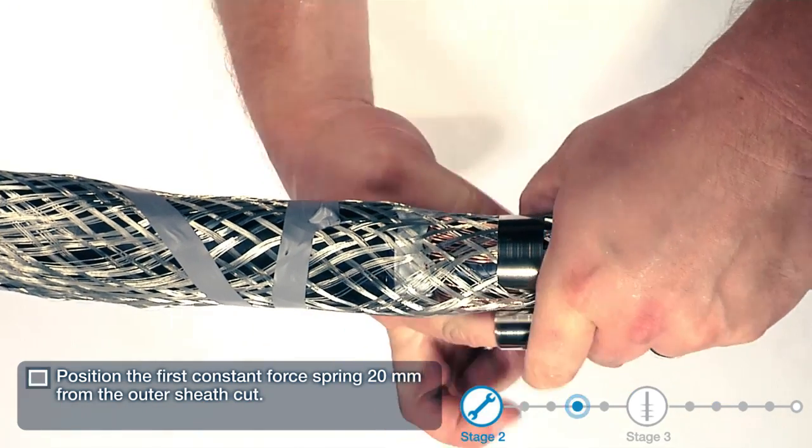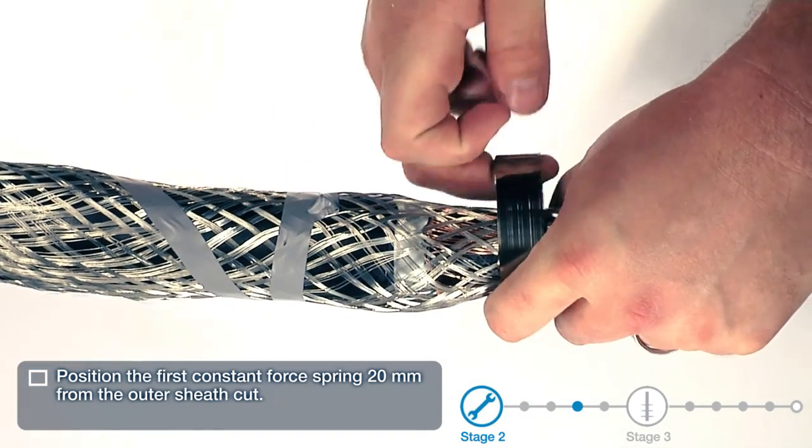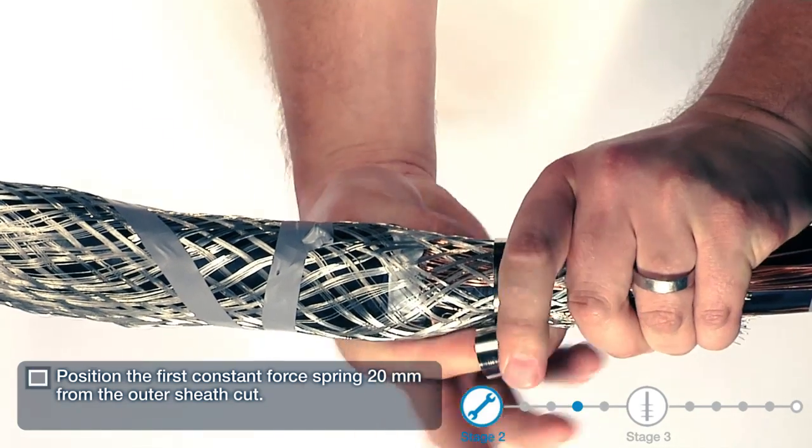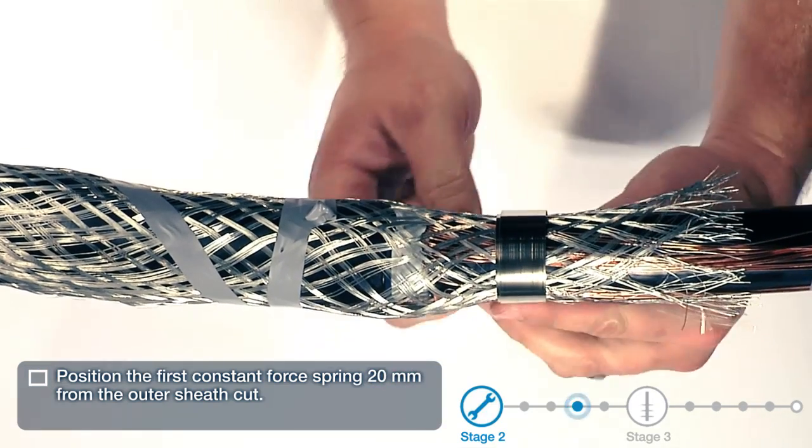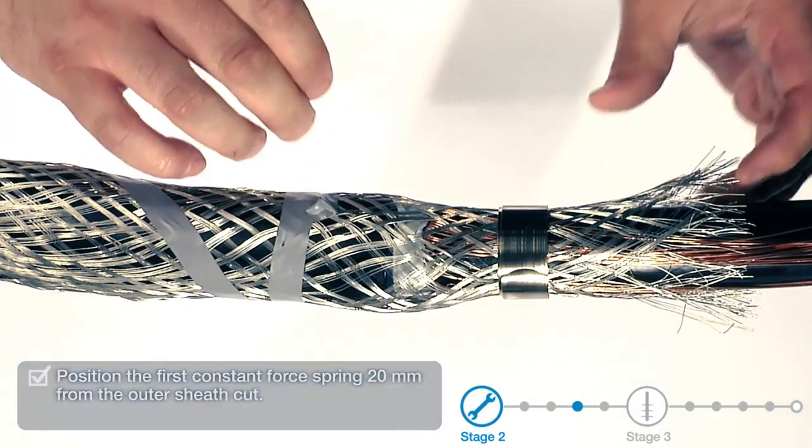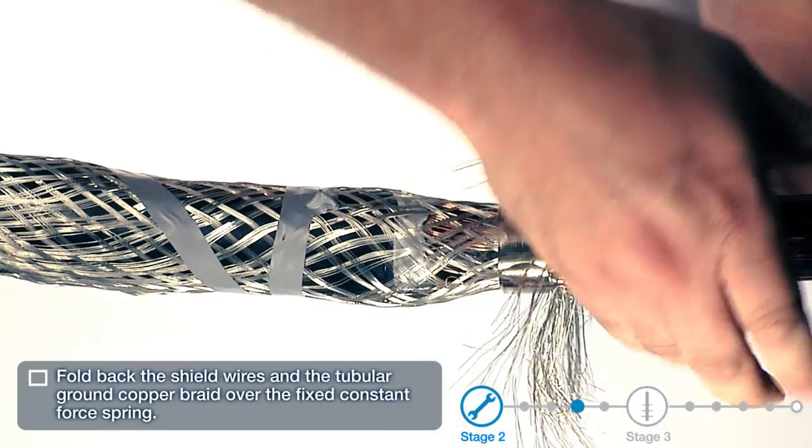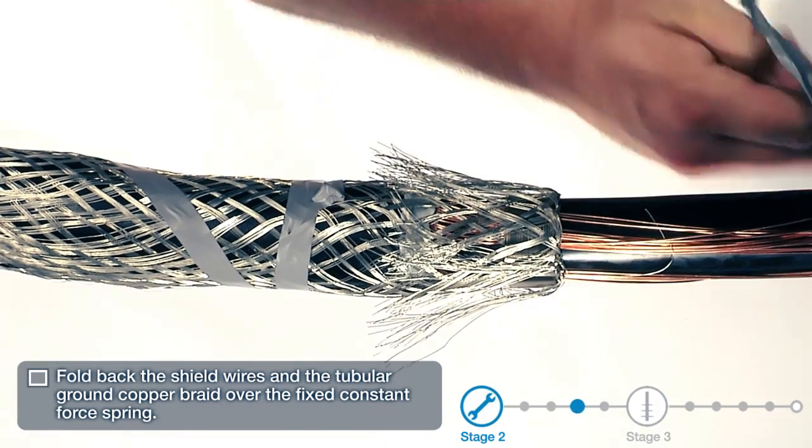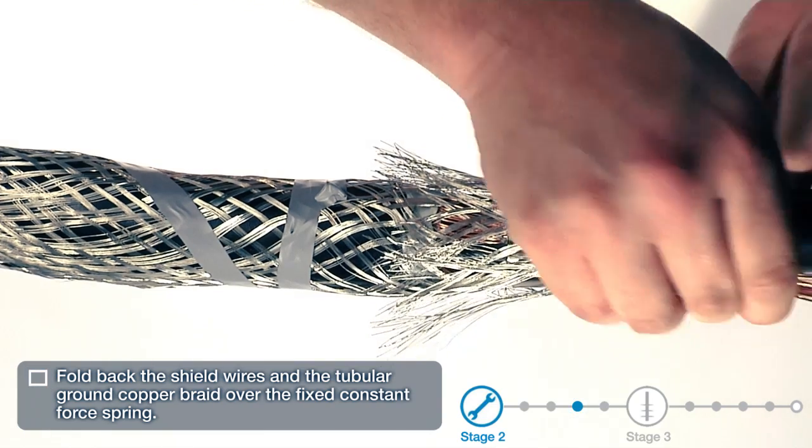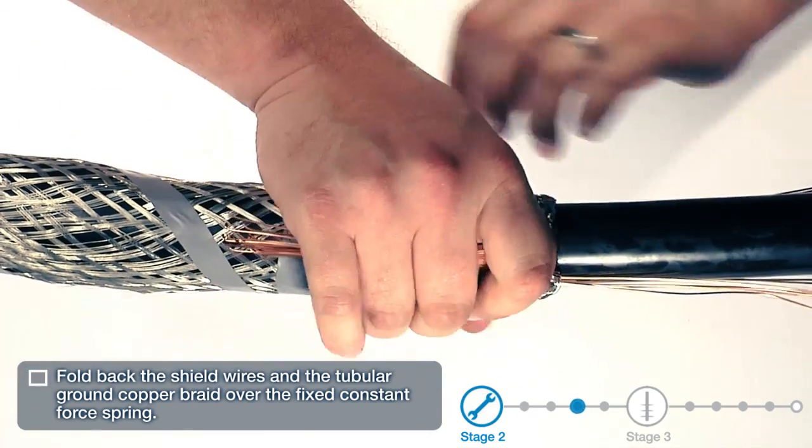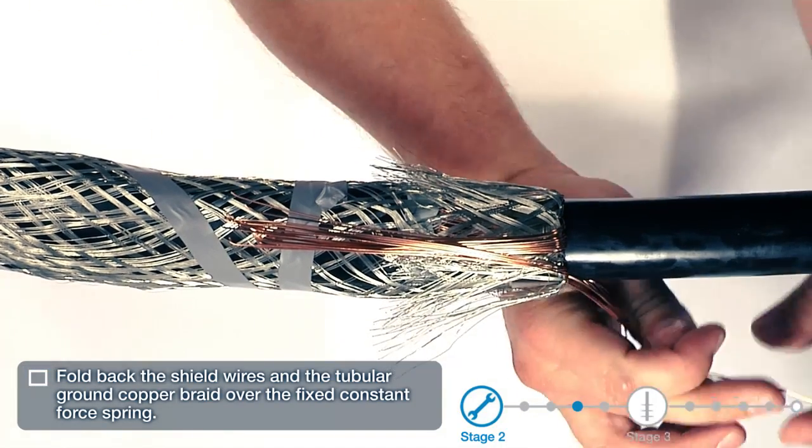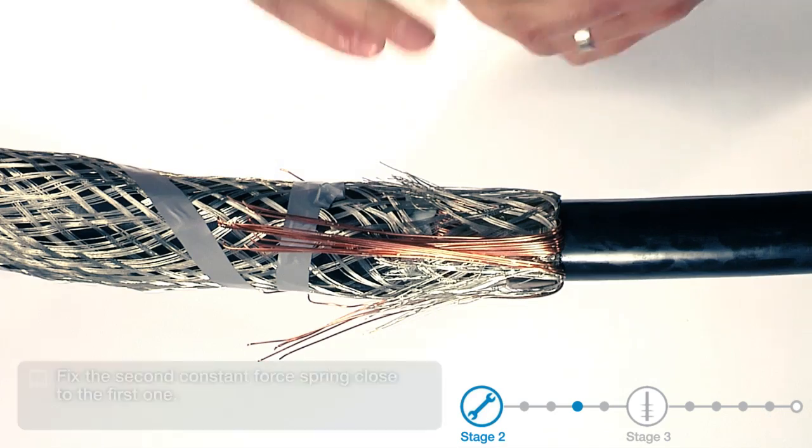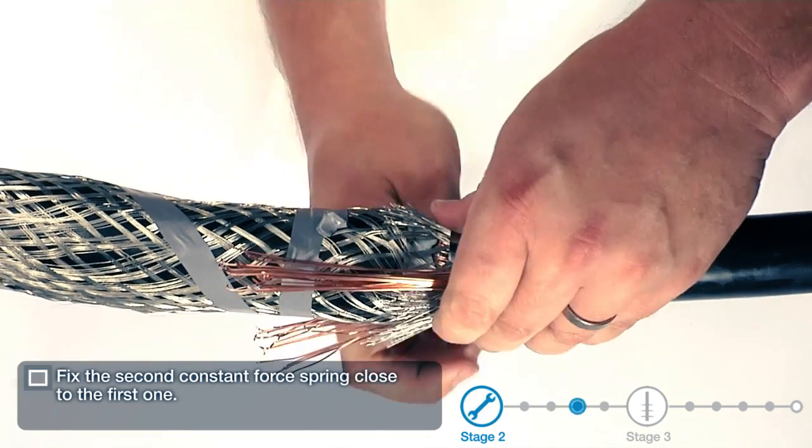Position the first constant force spring 20 millimeters from the outer sheath cut. Fold back the shield wires and the tubular ground copper braid over the fixed constant force spring. Fix the second constant force spring close to the first one.